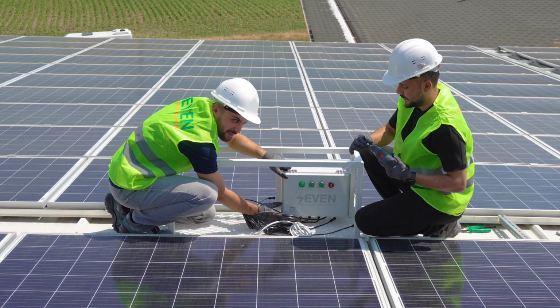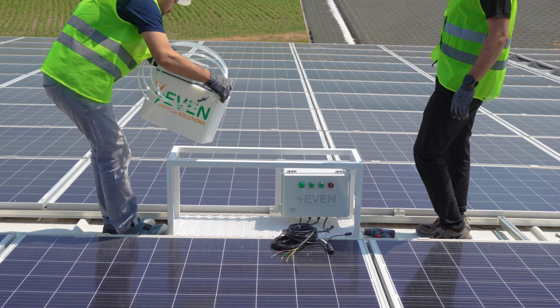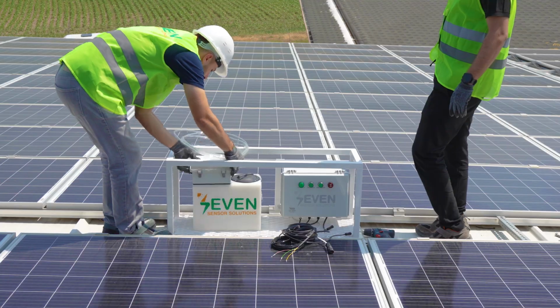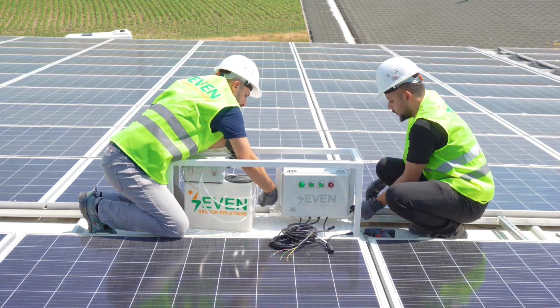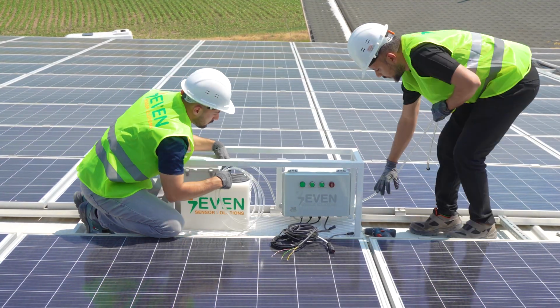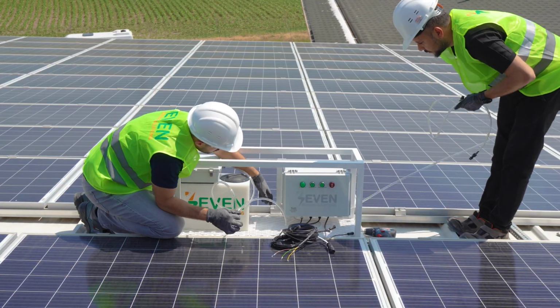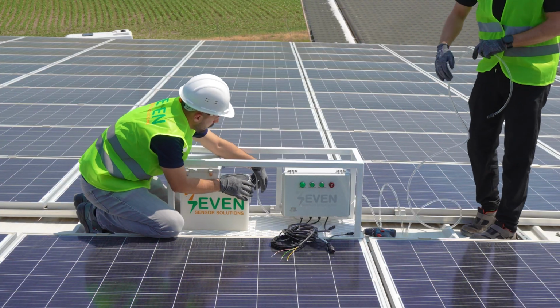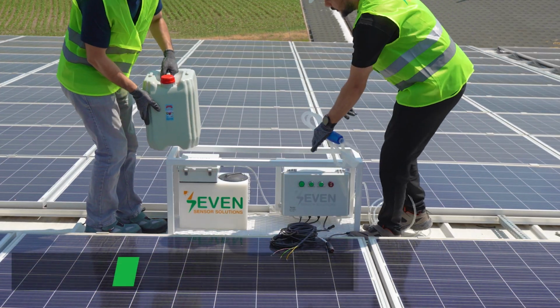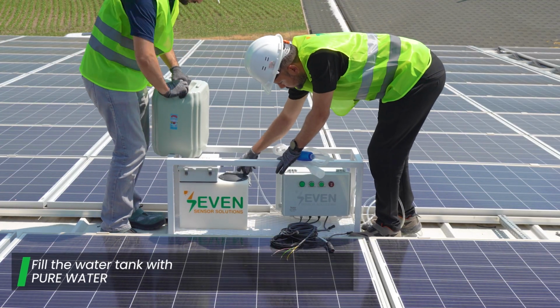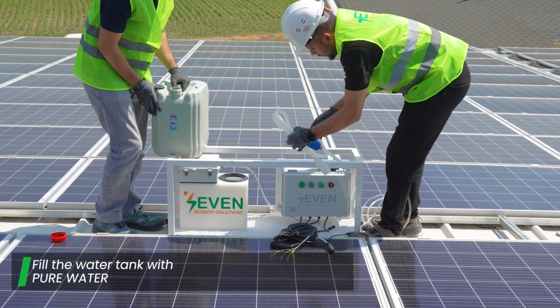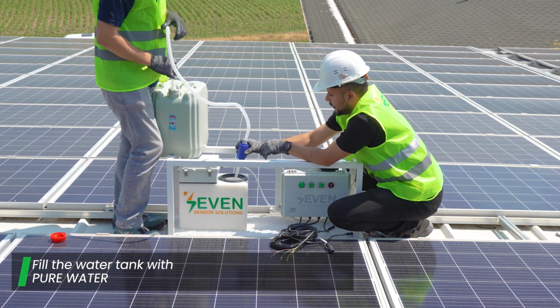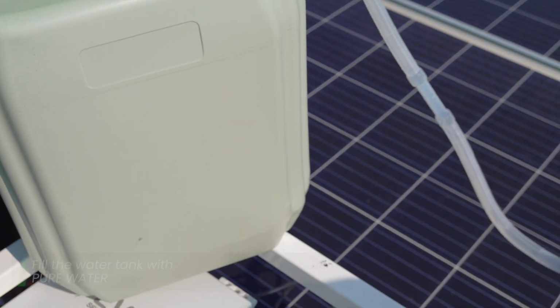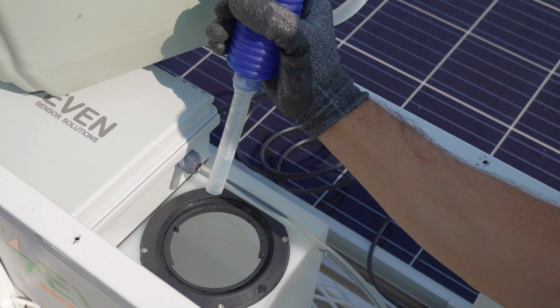If the site temperature is above 0 degrees Celsius, fill the tank with 100% pure deionized water. If the temperature is below freezing, use a 65% water to 35% antifreeze mixture, with high-quality antifreeze only. Avoid regular tap water or low-grade antifreeze, as they can cause stains on the irradiance sensors, severely affecting measurement accuracy.